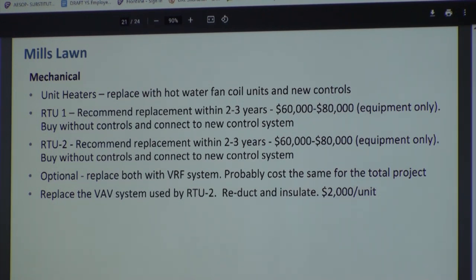And the other unit's a VAV system, right? Yes, and those are all 20 years old as well. Are they reheat? Do they have a reheat? They're tapped into the boiler, so they're hot water reheat. Yes, okay, that's why I would go back with that. That's a good system, good use, good control.